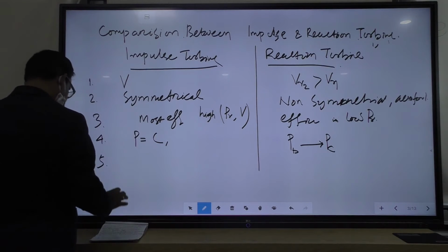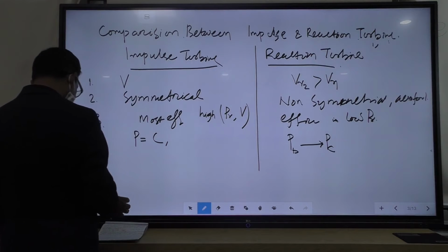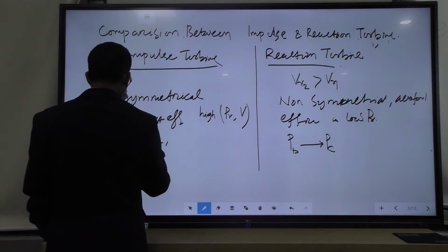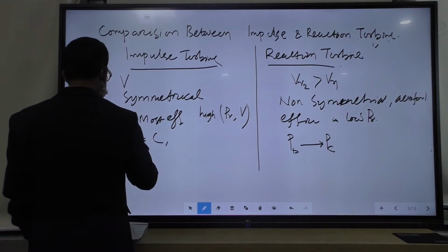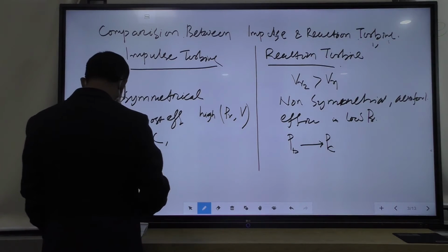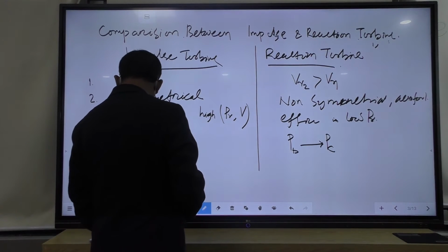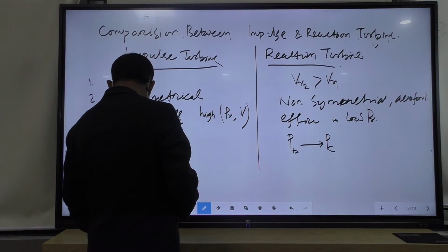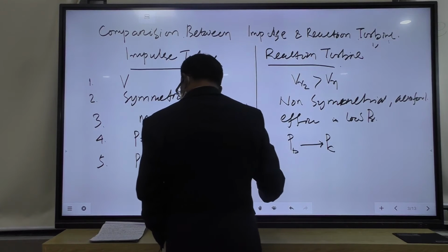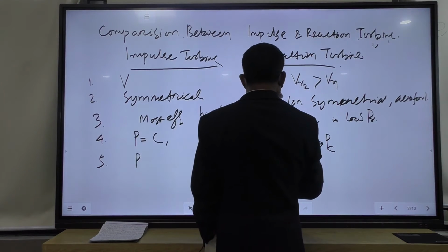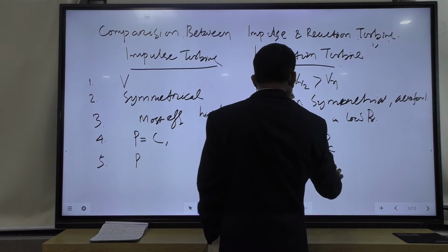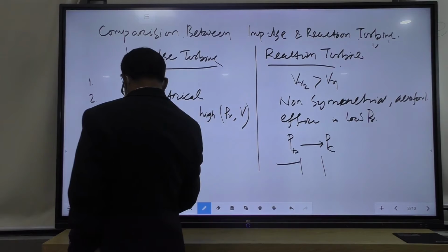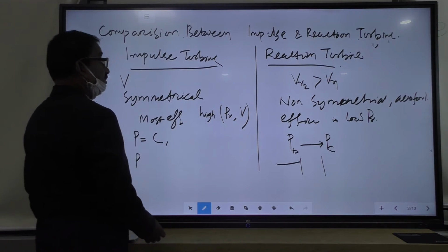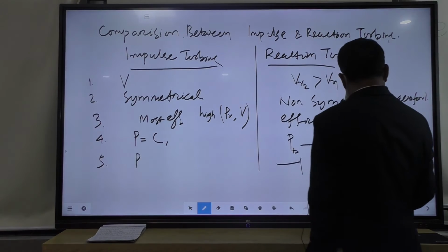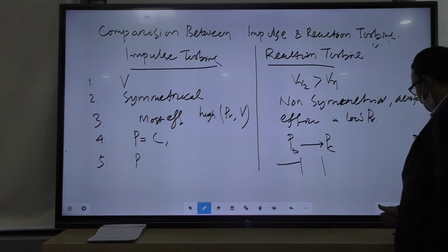Number 5, last one, efficiency is not maintained in the lower pressure stages. It is a high pressure turbine, so if the pressure is low, it is not efficient. In the same manner, the clearance can cause damage to the tips of the blading. So, due to these clearances between two blades, there can be damage to the blade tips. So, this is all about your comparison between impulse and reaction turbines.